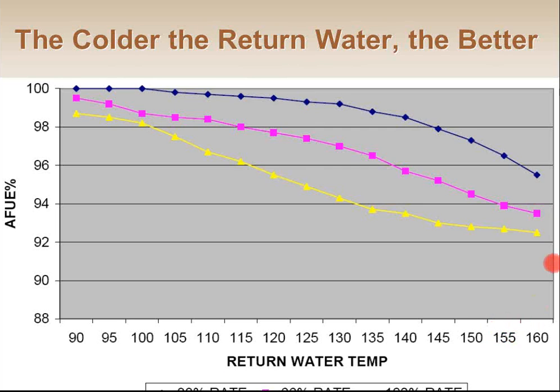Another 2% efficiency, right? And the reason for that is that my boiler has a certain size heat exchanger, and if I reduce the firing rate, I have more surface area of heat exchanger relative to the gas I'm burning. It's kind of like you want to think about it the opposite way. Keep the gas burning consistent and triple the size of the heat exchanger. That surface area would give me a lot more efficiency. It's kind of the same thing in reverse here.